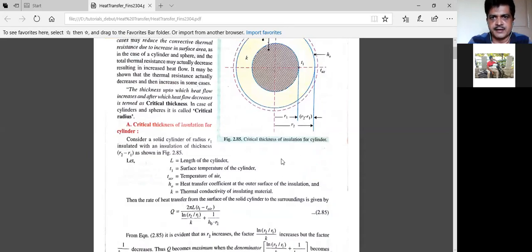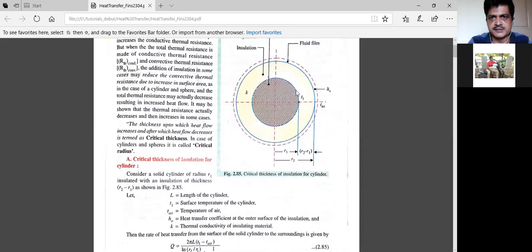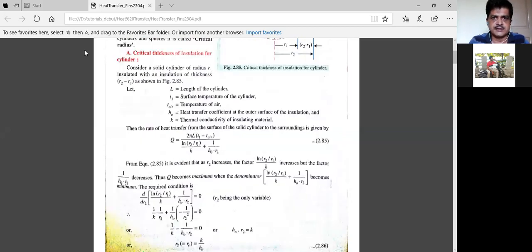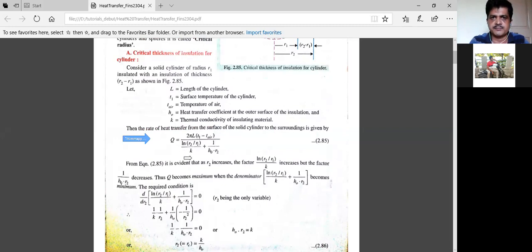The sketch shows r1 and T1 for the pipe, and outside temperature with convection heat transfer. The yellow color is the insulation material; L is the length of the cylinder. We already derived this equation: heat flow Q equals 2πL times (T1 minus T∞) divided by [ln(r2/r1)/k + 1/(h₀·r2)], where r2 is the outer radius of the insulation material and r1 is the radius of the pipe.